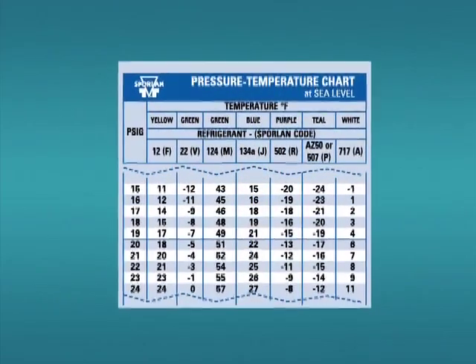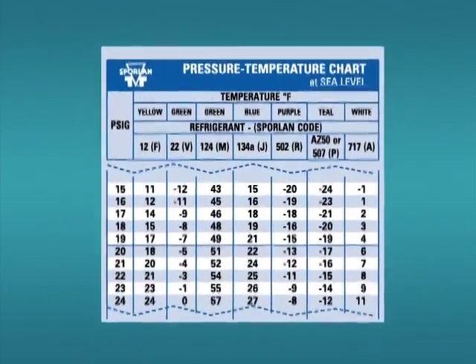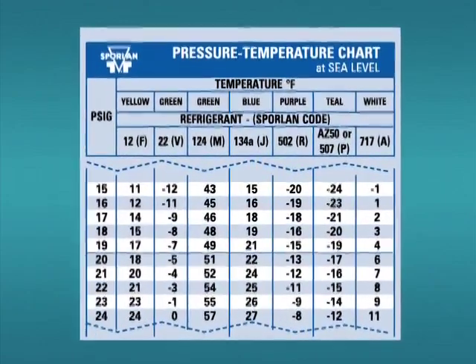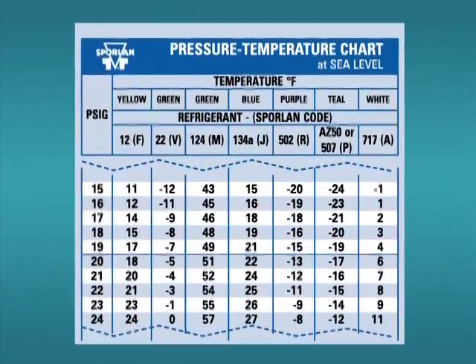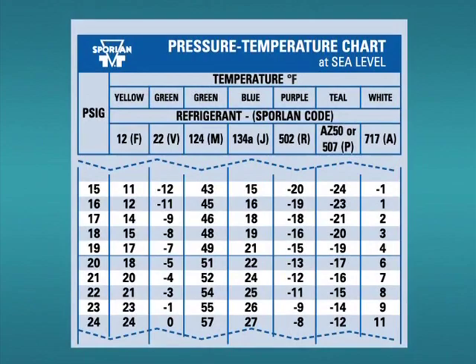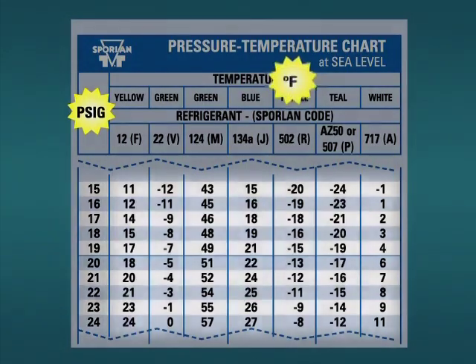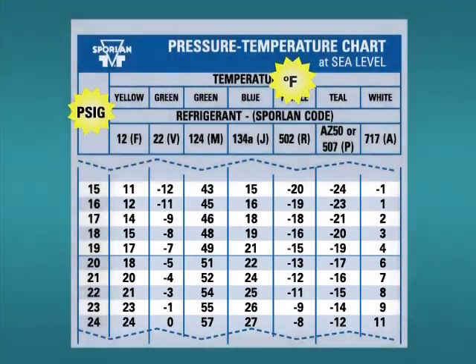The pressure temperature relationship as shown in the PT card is simply a chart listing the boiling temperatures of the refrigerant. By convention, a PT card has pressures listed on the left side of the chart and the corresponding boiling temperatures for each of the listed refrigerants on the right. Refrigerant at these conditions is referred to as saturated.